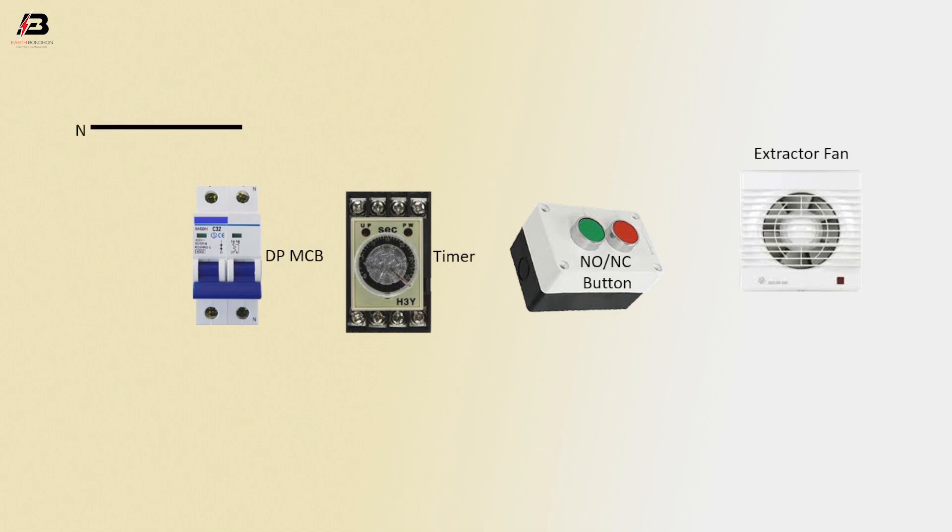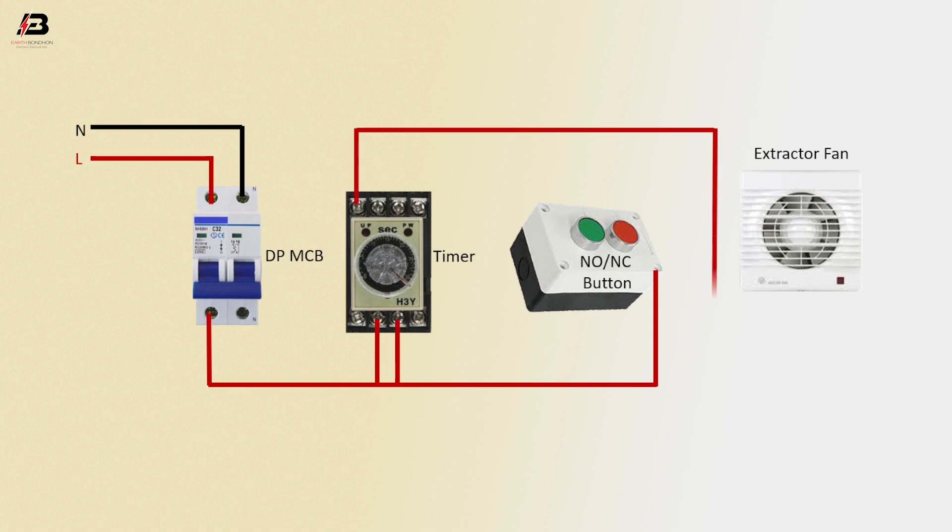Extractor fan. Neutral connection to double pole MCB. Phase connection to double pole MCB. Phase connection from double pole MCB to connect NO/NC button. Phase connection to timer. Phase connection output from timer to connect extractor fan. Neutral connection from double pole MCB to connect extractor fan.